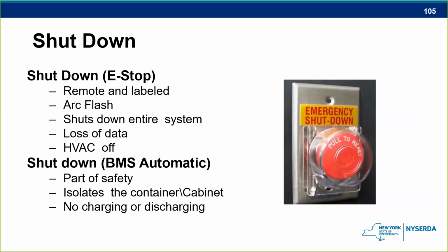If they shut it down and then that whole thing just stops, someone has to come back out there and do a full check on all 90 of these things, making sure they work properly before it goes back into service. So these emergency shutdowns, although they are good, we have to use them cautiously. If there was an incident that takes place inside one enclosure out of those 90 that I just mentioned before, the BMS should have picked it up, and the BMS should automatically shut that down. But I can tell you this, when firefighters see an emergency shutdown button and it's electric involved, they're shutting it down, because they usually give a communication on the ground to everyone, power's shut off, and that's what they do. That's very typical. I don't blame them for doing that. That's what they've been taught since their fire academy days.